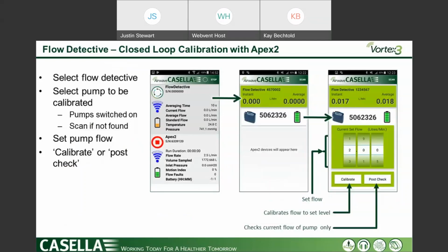You can pull up, it does it as a separate aside. So you'll see the Apex 2, like what's listed here on the slide. You'll see your Apex 2, you'll see your Vapex, and you'll see your Flow Detective. Then you select Flow Detective, and it will automatically find the different pumps available to calibrate. You check your serial number, cross-check it to make sure you have the right pump selected, you press calibrate, and then you email yourself the report. It's that simple.